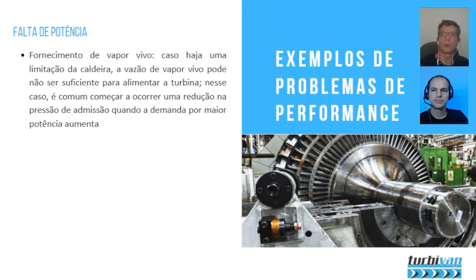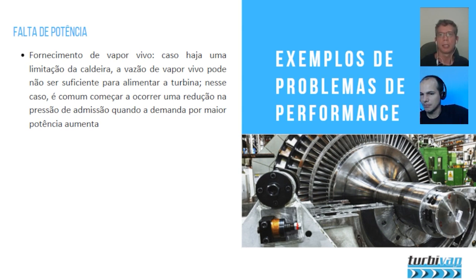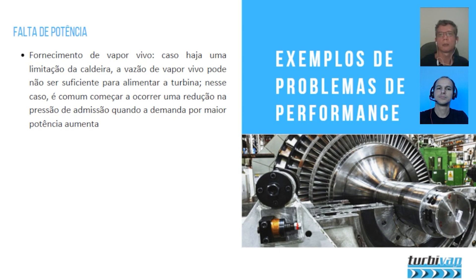Another common problem is with the steam supply. When the machine reaches nominal power, you expect live steam pressure to remain stable. If pressure begins to drop as the machine approaches rated power, it indicates the boiler is at its limit — it can no longer maintain the design pressure at that flow. This could indicate a design problem: the boiler was purchased at the limit of its supply capacity, or a boiler previously sized for a different turbine was repurposed without adequate reassessment.